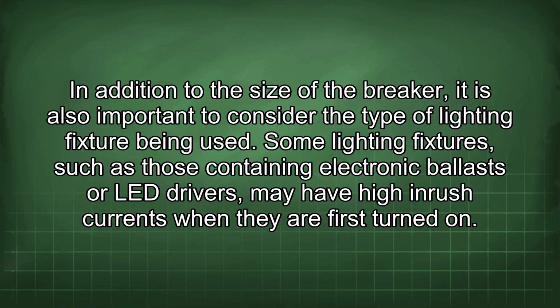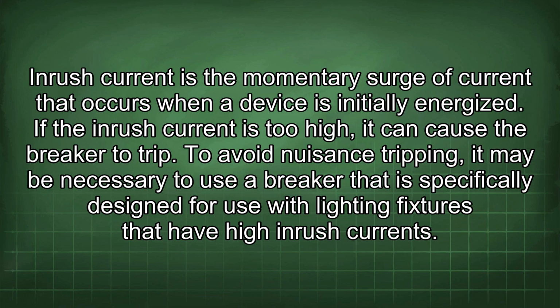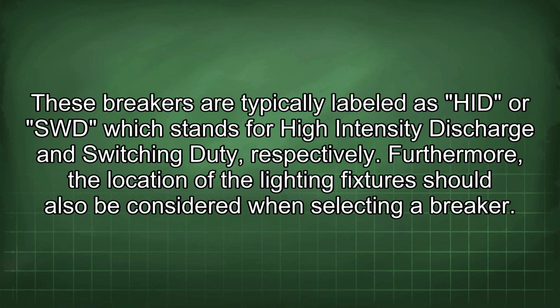In addition to the size of the breaker, it is also important to consider the type of lighting fixture being used. Some lighting fixtures, such as those containing electronic ballasts or LED drivers, may have high inrush currents when they are first turned on. Inrush current is the momentary surge of current that occurs when a device is initially energized. If the inrush current is too high, it can cause the breaker to trip. To avoid nuisance tripping, it may be necessary to use a breaker that is specifically designed for use with lighting fixtures that have high inrush currents. These breakers are typically labeled as HID or SWD, which stands for High Intensity Discharge and Switching Duty, respectively.